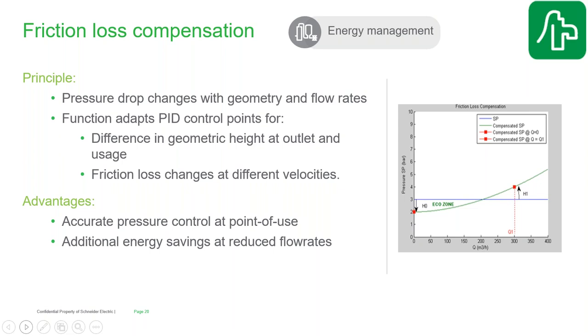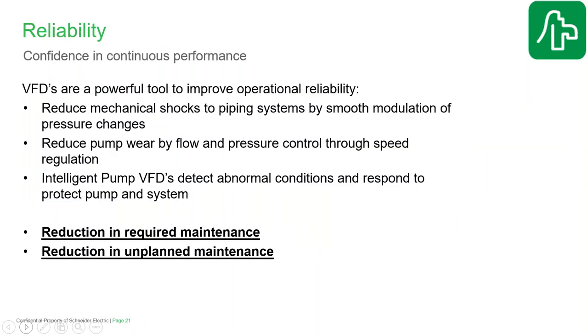So if the flow rate is varying, for example, if you are using different numbers or different amounts of irrigation sprinklers at any one time, the drive can automatically adapt and regulate the pump output pressure to different levels to ensure you have correct pressure at point of use with the minimum energy requirement. From a reliability side, this is critical in any irrigation application, because you need to be confident that when you think you're running your irrigation systems, you are in fact actually running them, and it is delivering the correct amount of water where it needs to go. And VFDs and the intelligent VFDs of today can be a very powerful tool for improving this reliability.